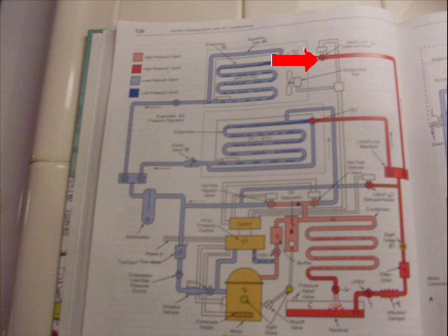And now we're going to go up and we come to a T in the line, refrigerant splits. On our way for the liquid refrigerant up to the top evaporator, the high temp evaporator, we go to a liquid line solenoid valve. Liquid line solenoid valve's job is to turn on and off the flow of liquid to the high temperature evaporator. The liquid line solenoid is controlled by a thermostat or cold control. If the temperature in the box is cold enough, the cold control or thermostat will shut off the liquid line solenoid valve and it will stop the flow of liquid.